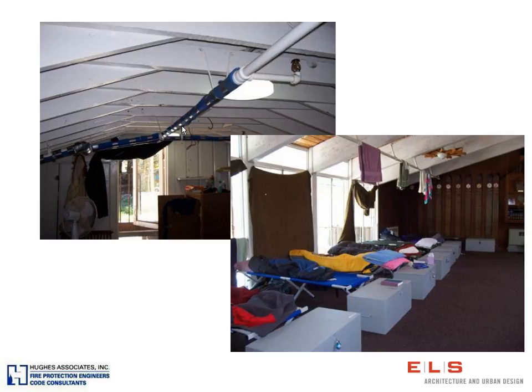Well, I think the two points you've made are really important. The first one here, where we have issues with wood-sided buildings or wood frame buildings and what we call Type 5 buildings, which is the area allowable. For example, even that old administration building that was predominantly masonry construction, because of the mixed construction of the wood floors and the wood trusses and everything, it was over area. And by putting in the fire suppression system, it allowed us to keep the building.